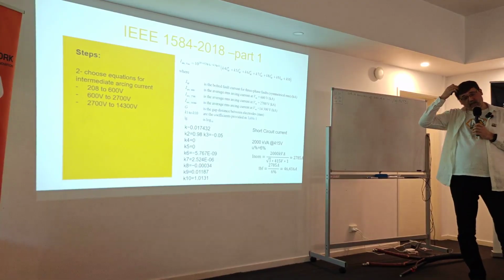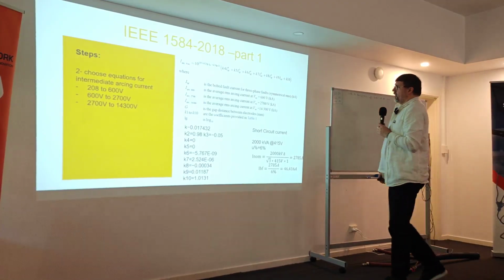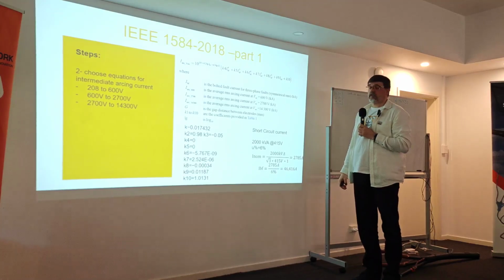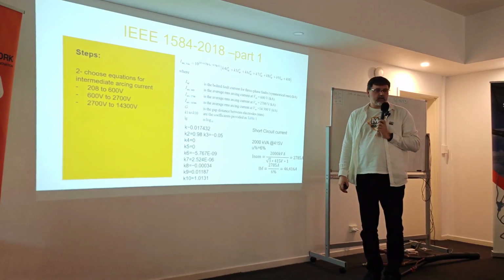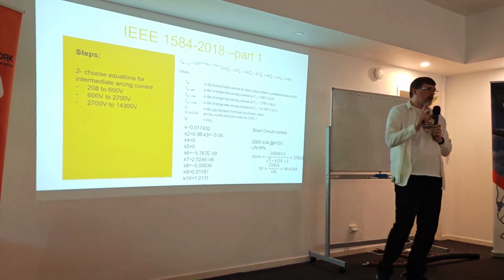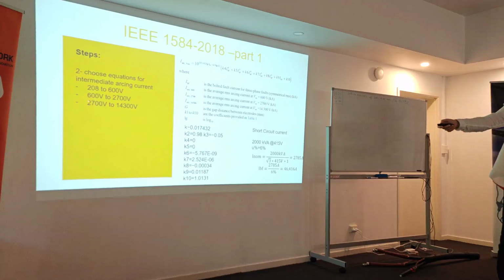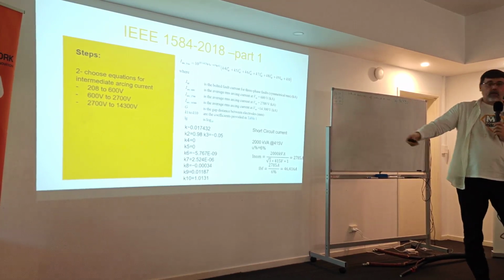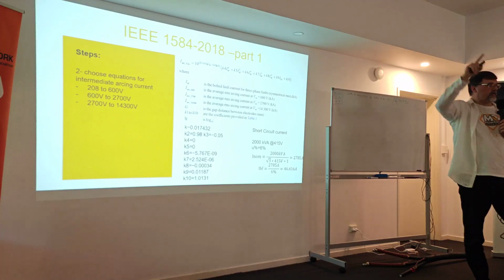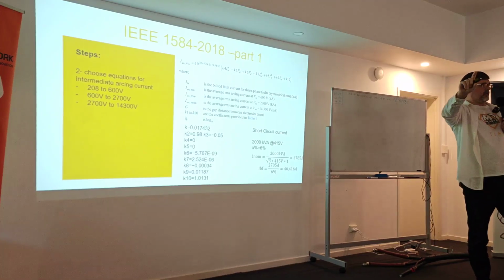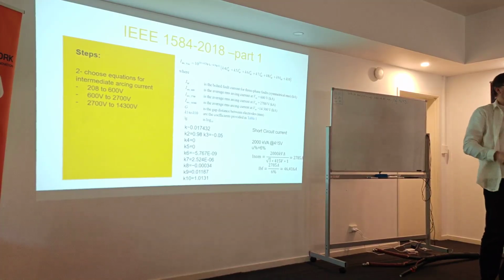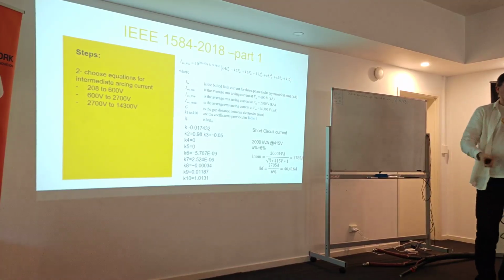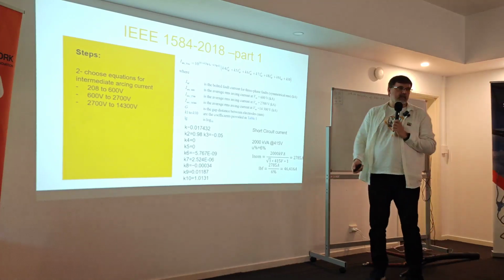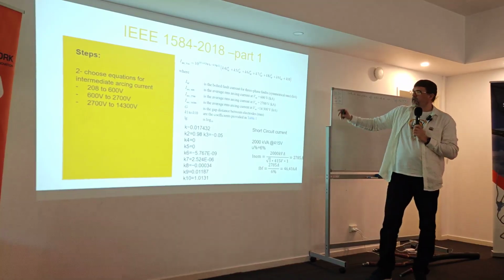But you can see there's a lot of others, yeah? So that was the first one. That's the first equation that we have to use to calculate it. First, intermediate arcing current, and it's called intermediate because I especially choose 415 volts, so we do one step. But if you choose something like 6.6 kV, then normally the equation works like this: you calculate two of these, and you interpolate the results in between. You just take the one result, the second result, divide it, and then you have a value, and it works for everything like this. So you do two calculations, and the third one, which is the final one. When I do below 600 volts, I can do one calculation only, which is easier for the example for today. So that's the first calculation.